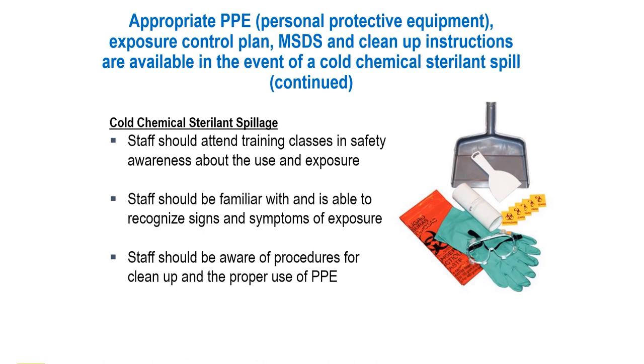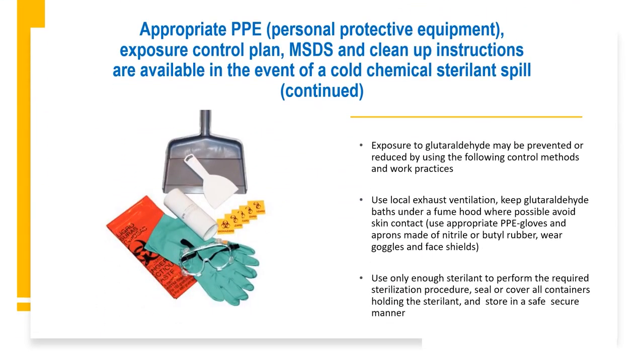These cleanup procedures include wearing appropriate PPE to include gloves and aprons made of nitrile or butyl rubber, goggles, and face shields. To reduce exposure and provide safety for staff exposed to harsh chemicals, an exhaust ventilation system is recommended. Keep glutaraldehyde baths under the fume hood where possible, and avoiding skin contact are best practices. Using only enough sterilant to perform the desired outcome is important, and always keep the holding vessel of the sterilant sealed or covered. Adhering to these procedures will ensure safety for your staff and members.